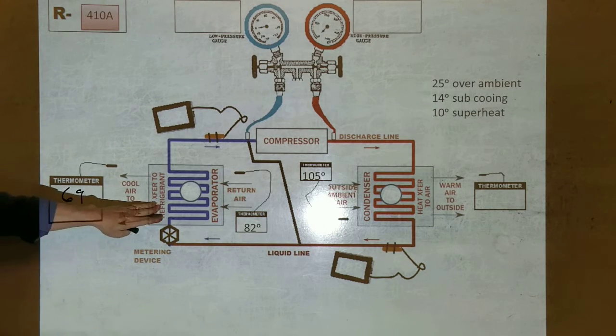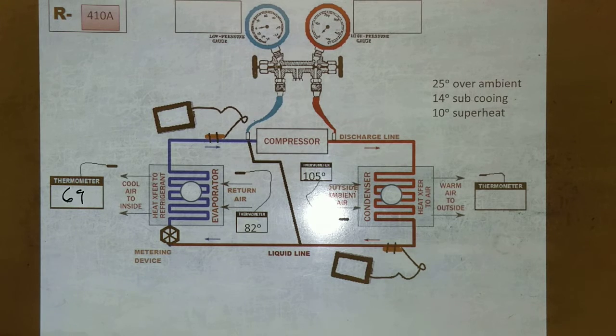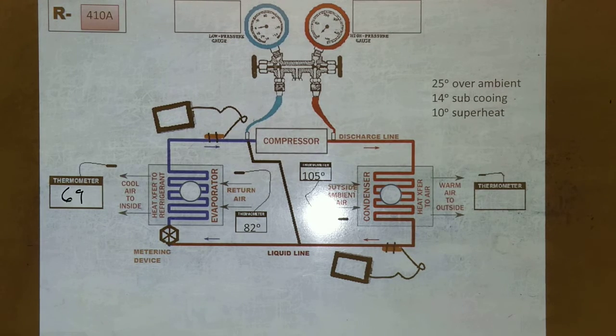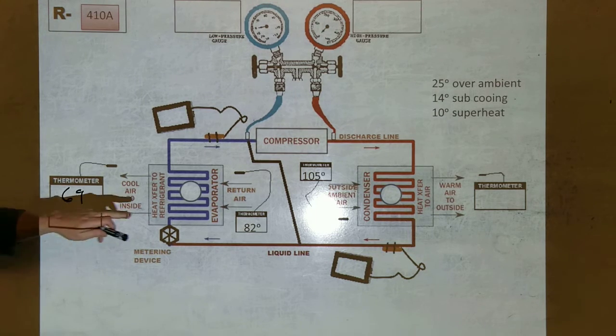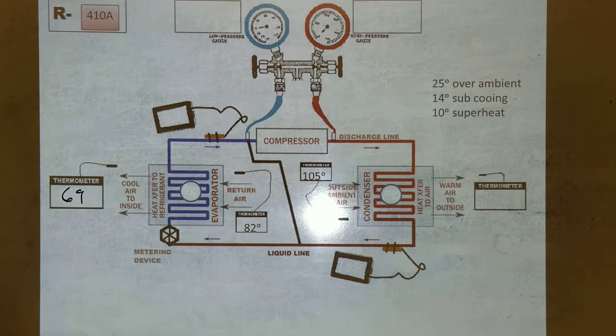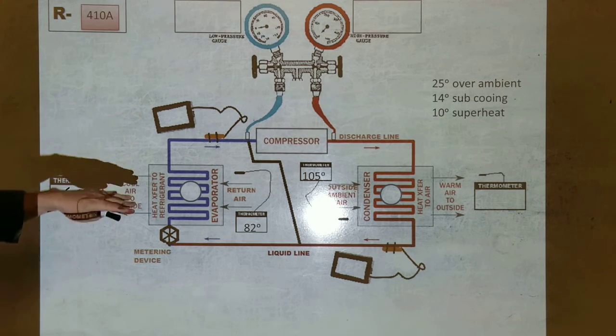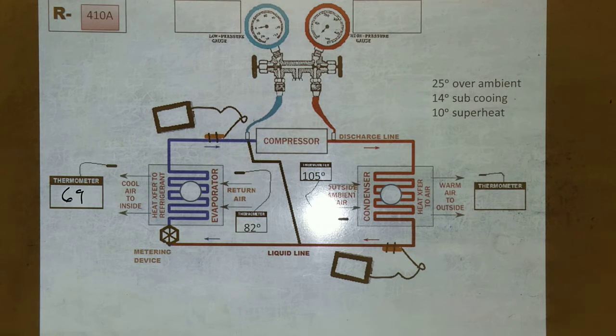But when I did service out in the field and I was servicing a bunch of units, instead of putting my gauges on every single one of them, you just check the temperature. I checked the temperature split, that delta T. If I got 20 degrees, I know that the refrigeration side is running fine. Perfect. So then I can spend the time looking at the electrical connections and stuff like that.